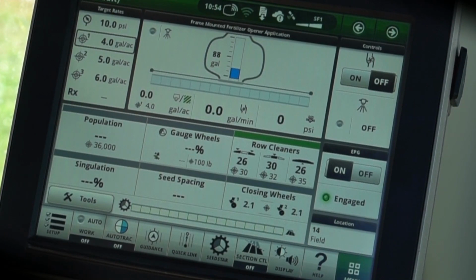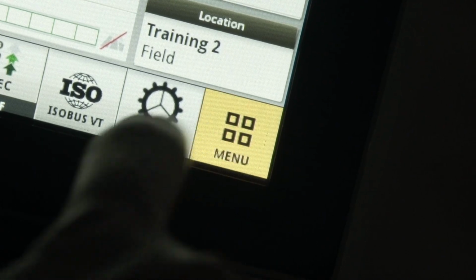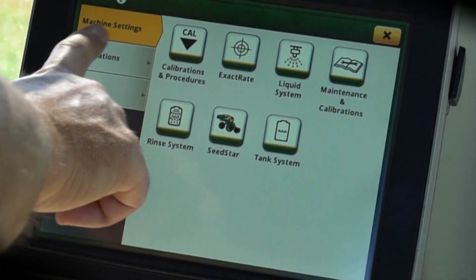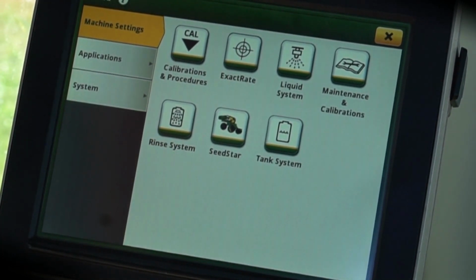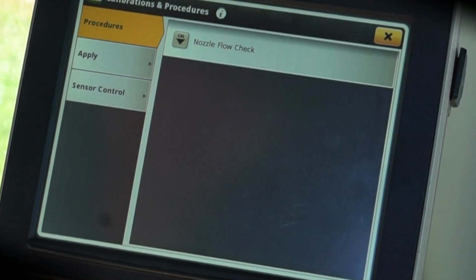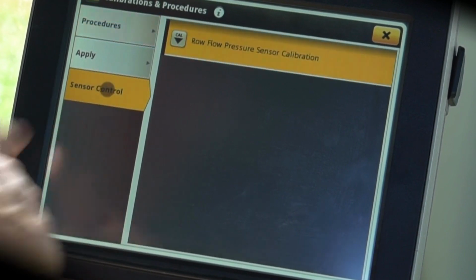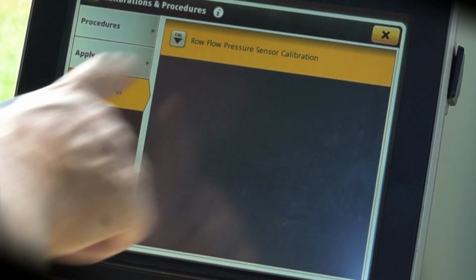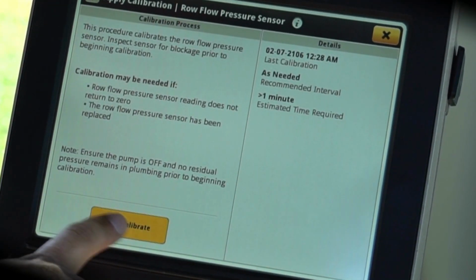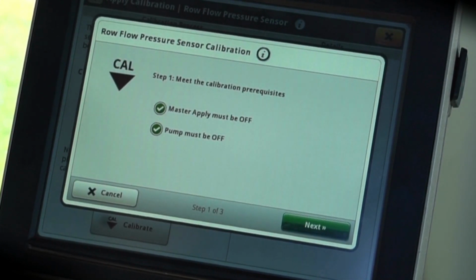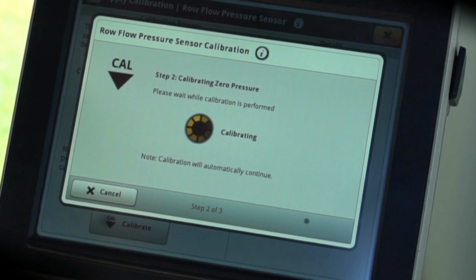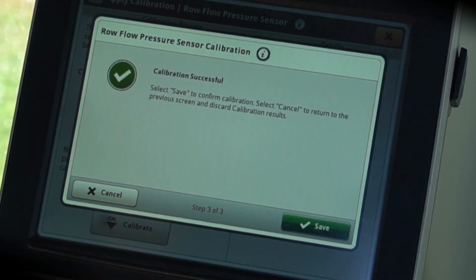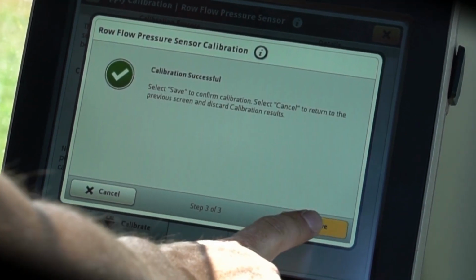To do this on the display, open the menu and choose the Machine Settings tab. Open Calibrations and Procedures and choose the Sensor Control tab. Press on Row Flow Pressure Sensor Calibration. Press the Calibrate button. Verify that the prerequisites have been met and press the Next button. All pressure sensors will be zeroed.